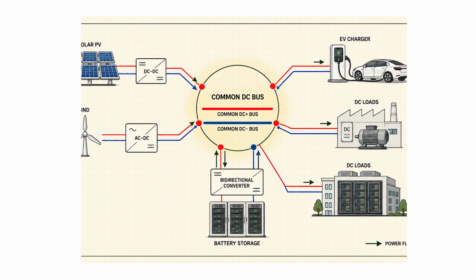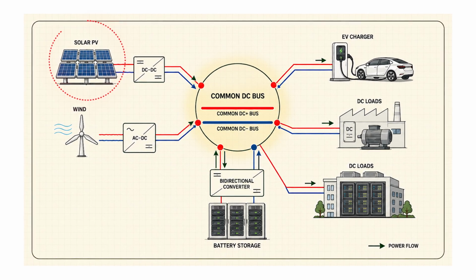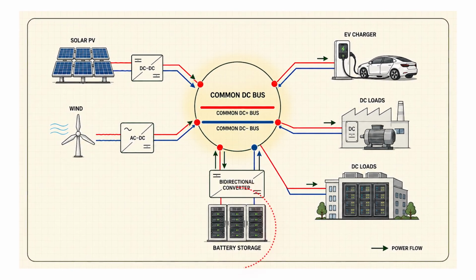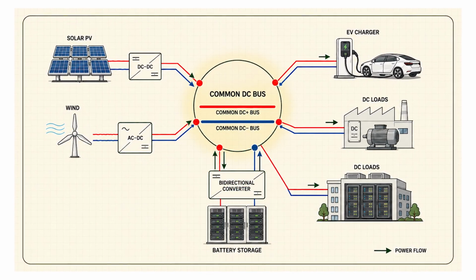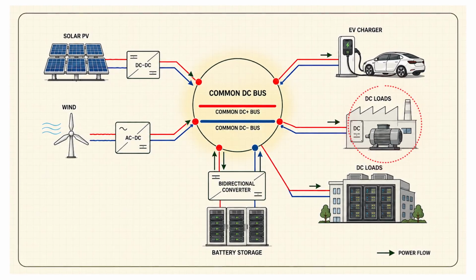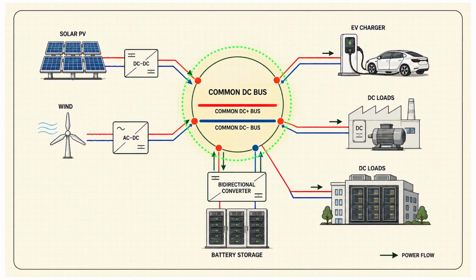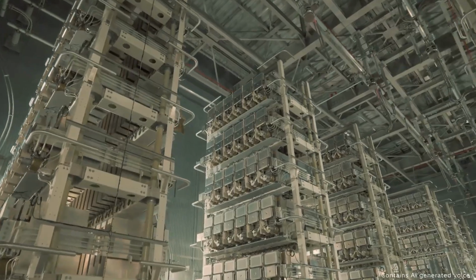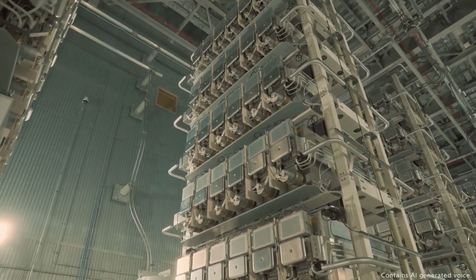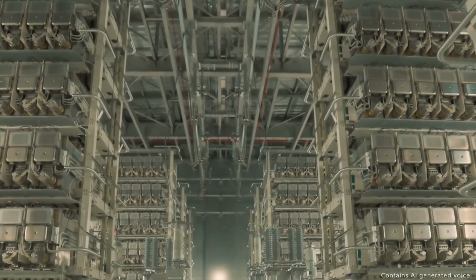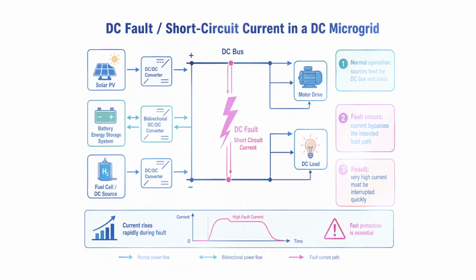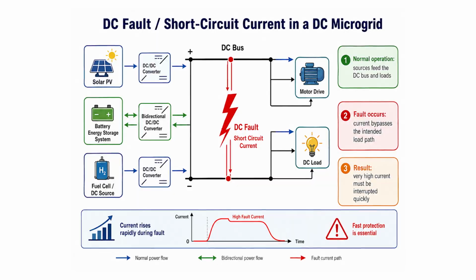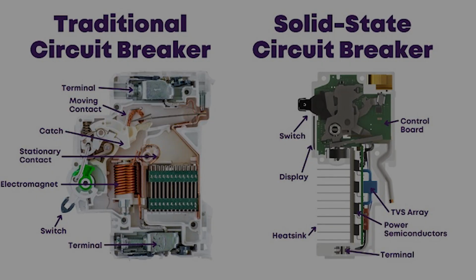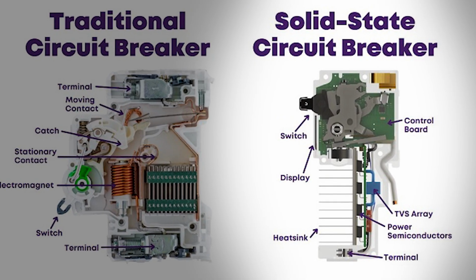Another rapidly growing industry is DC microgrids, which contain solar generation, wind generation, power converters, batteries, and multiple complex loads connected to the same DC distribution network. These applications are different, but the problem that needs to be solved in high voltage DC distribution is the DC fault current and short circuit current. And that is exactly where the solid state circuit breaker enters the market.